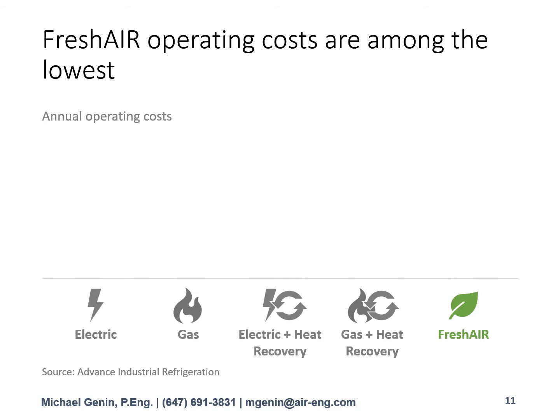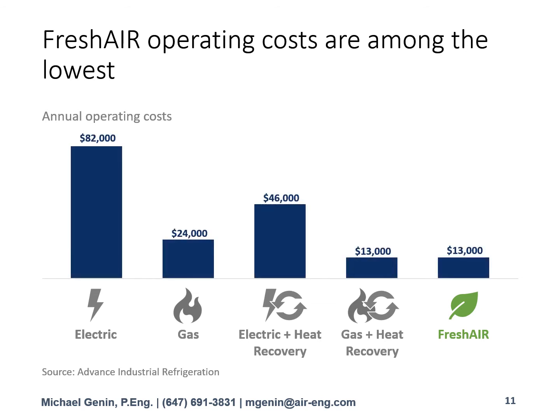So in this example, using the same 11,000 CFM, we ran the numbers for different situations: electric, gas, electric with passive heat recovery, gas with passive heat recovery, and then fresh air active heat recovery. And the results are as follows, and these are using Ontario electric and gas costs. So electricity is by far the most expensive, about, as we discussed, 3 to 4 times the cost of burning natural gas. And when we move to the passive heat recovery, you can see they take a sizable dent in the total amount of energy use, which is expected.